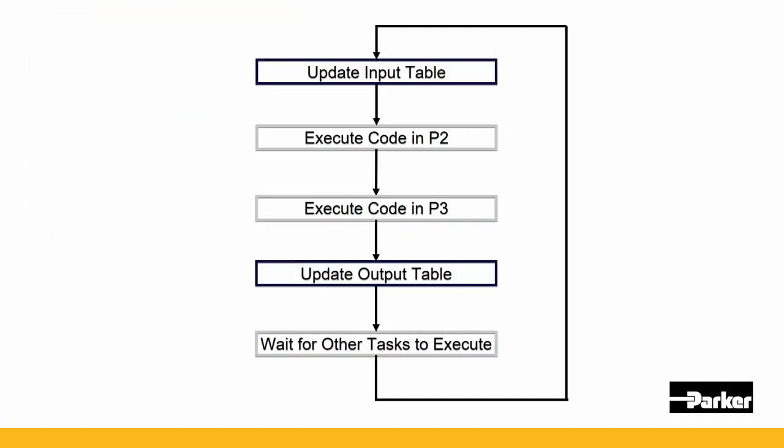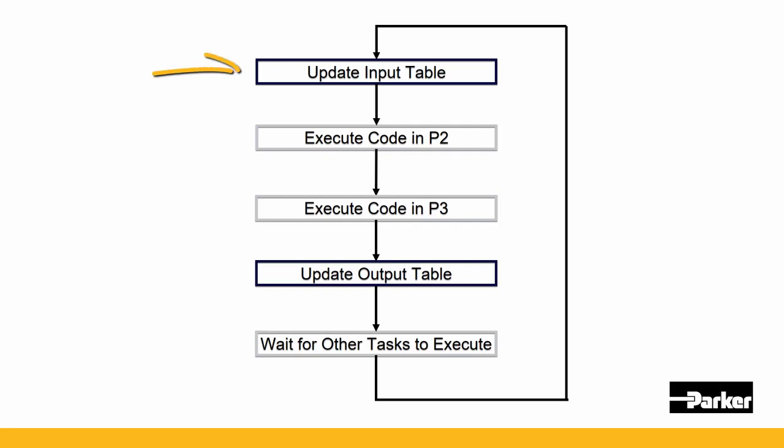Remember, this task does not have an EtherCAT scan. So the EtherCAT input variables are the same as the last EtherCAT scan and will not be updated until the next EtherCAT_task scan is executed. Non-EtherCAT inputs are updated at the beginning of this scan.